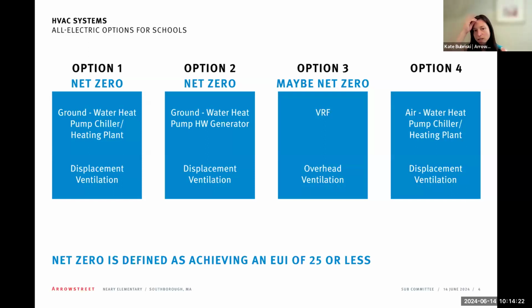So the four systems that we typically look at for a school building are options 1 and 2, which are ground source systems. I'm assuming you're all familiar with ground source, but essentially it's closed loop wells that go down into the ground. They're not transferring water with the ground. But those wells use the ground and the temperature in the ground as a heat transfer. So whether you're doing heating season or cooling season, you have that fairly stable ground temperature, which helps improve your efficiency. And the ground source systems are the most efficient systems because of that.